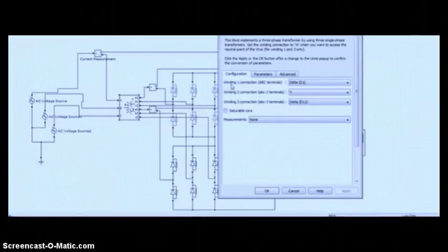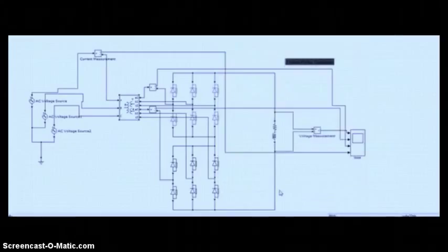So what I have made is I have used a delta connection for our primary, and for the 2 secondary, one is Y connected and the other one is delta D11, which you can go in the help and see what it actually means. So what we use is 2 6-pulse or 3-phase bridge rectifiers and connect them in series or in parallel, in either mode we need, if we need a high current or high voltage.